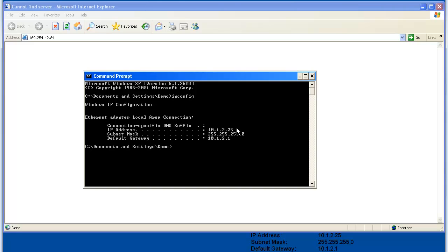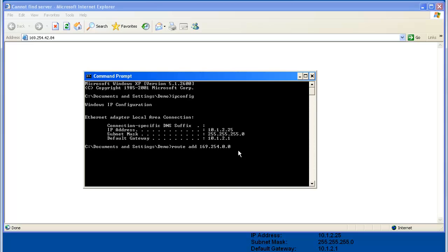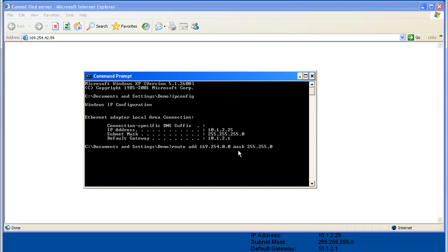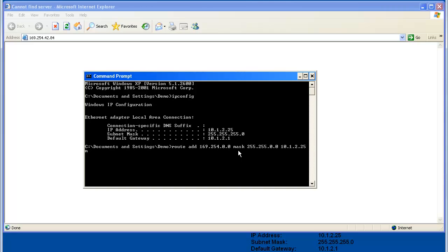This is the address the computer is using, so when you find your address, write it down. Now I'll enter a command that will tell the computer to route the ANX2 module's link-local address. Type: route add 169.254.0.0 mask 255.255.0.0, then a space, then enter your IP address, then space, and then metric 20. Hit enter.